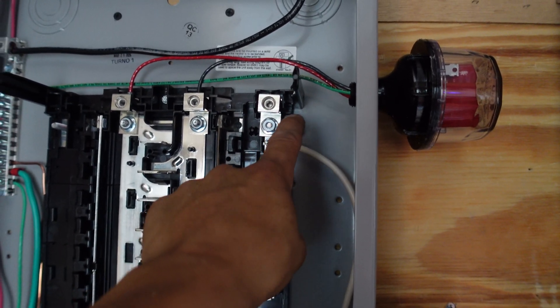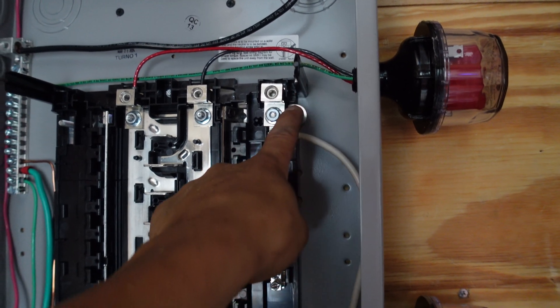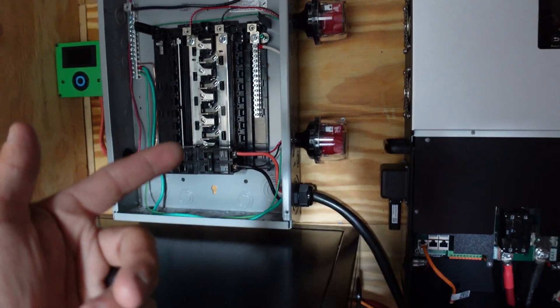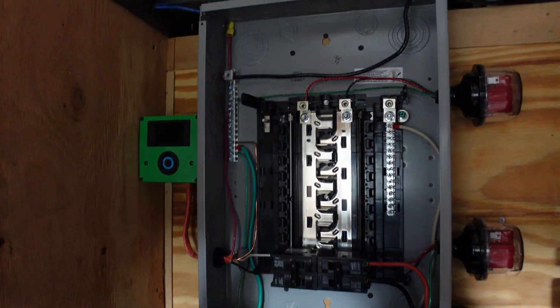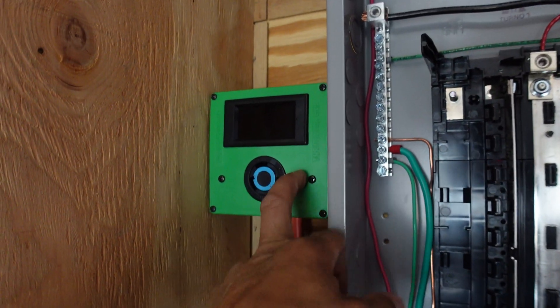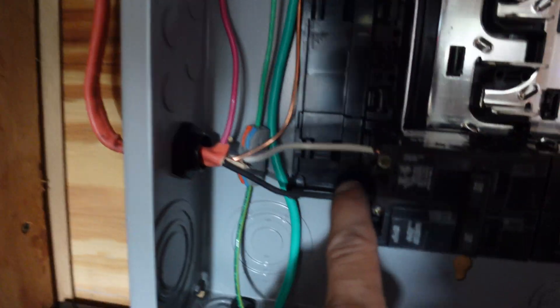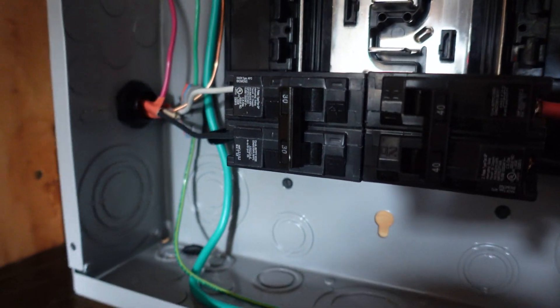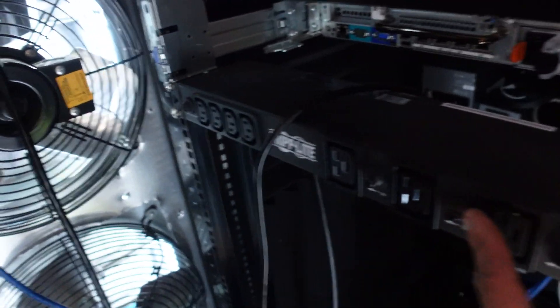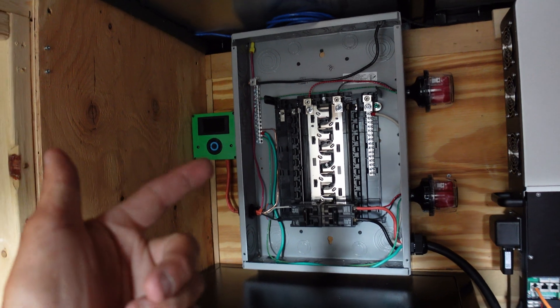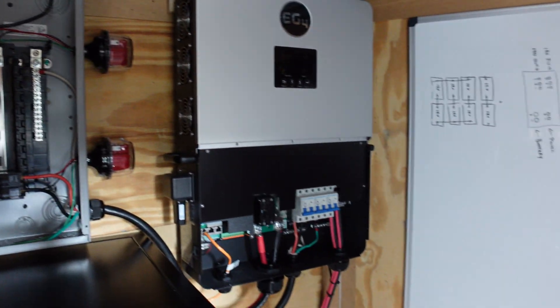And then last but not least I have the neutral bar that really doesn't do anything to be honest. So I just have that wire going from here to that spot right there. And you don't want to tighten this nut, right? This will actually make a ground neutral bond, you don't want to do that because the 6000 XP actually does that internally by itself, there's a setting in there. And then I have the 30 amp PDU outlet right here that is being fed with 240 volts as you can see, 30 amp breaker. That's going to be this guy right here, I'm going to be utilizing it for the KS zeros and my brand new AL box too. Let's fire this up because I haven't done it yet.